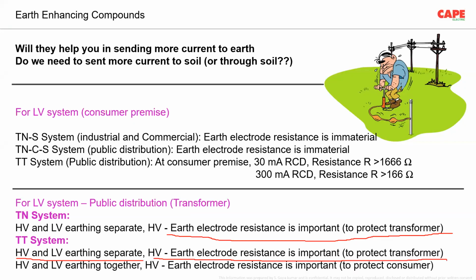If they go for HV and LV earthing together, that means the HT side and the LT side earthing is connected together. In that condition, earth electrode resistance is important to protect the consumer premise. Consumer premise means our houses. What does this mean is, electricity can be supplied from the transformer under several methods, TNS, TNCS, TT and all. If the distribution company is using a TN system, and if they want to make HT and LT earth electrodes separate, then of course the HV side earth electrode resistance is important.